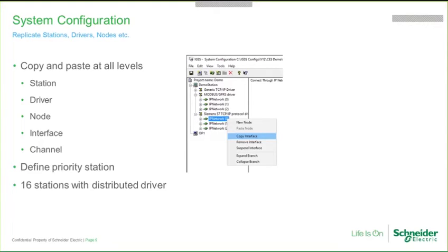Also, you can now define a station to be a priority station. That's one of the check marks on the station tab. Priority station means that this station will not be disconnected when trying to regain station connections. This is used in the instance where you actually have more stations connected than the license you have purchased. Some customers only purchase, for instance, 4 operator stations, but then actually connect more than 4 stations. IGSS handles that by disconnecting the stations that has been idle for the longest time.